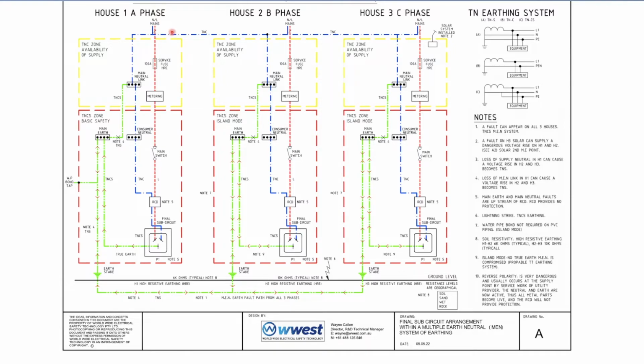It's something that happens out in the utilities area in the street, the poles or the transformer or something like that. But if you think about reverse polarity, think about that neutral now is active, then all these are livened up to 240 volts all the way through. And there's been a number of recorded accidents that have happened because of that.